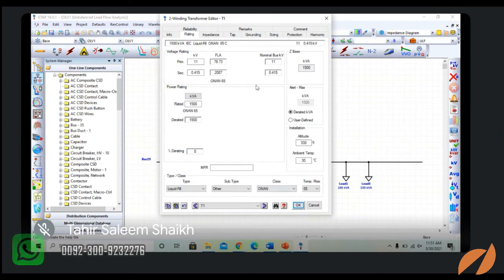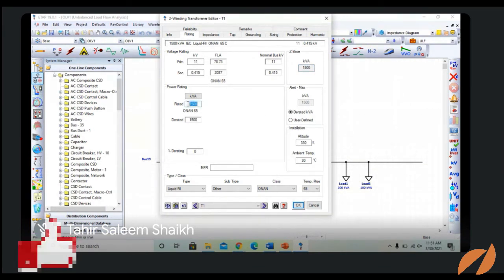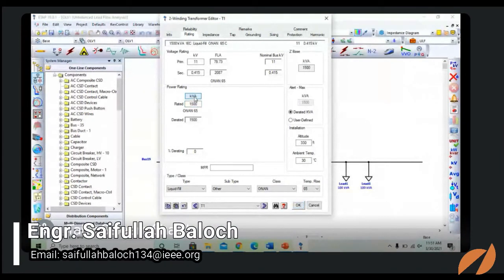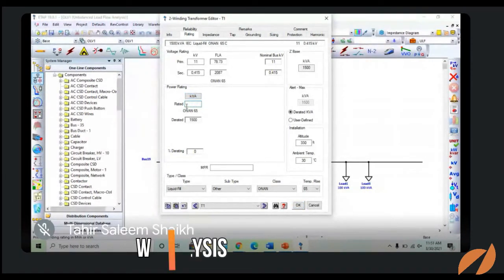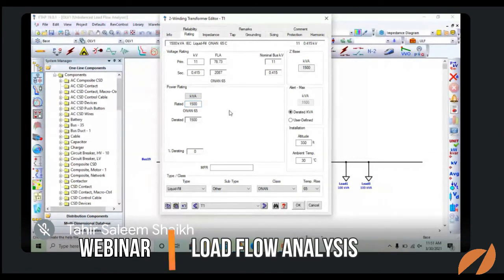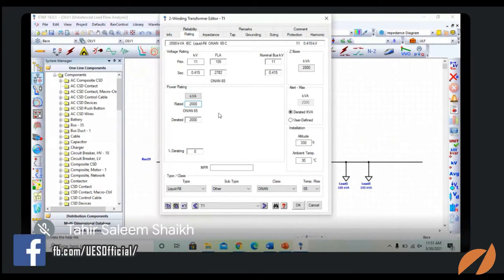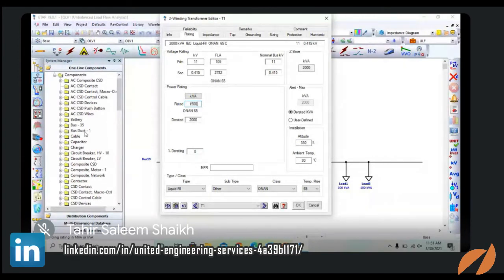Now here we have the kVA for this transformer. If you want to change it, you can change it here. Power rating: if you want to put it in MVA or kVA, or change the rating, for example 1500 kVA, you can change it. You can also put 2000 kVA. Here you can see the data is changed; the full load amperage is automatically changed. Just after I change the power rating, it will automatically change the primary rated current and the secondary rated current. Now here we are selecting 1500 kVA.